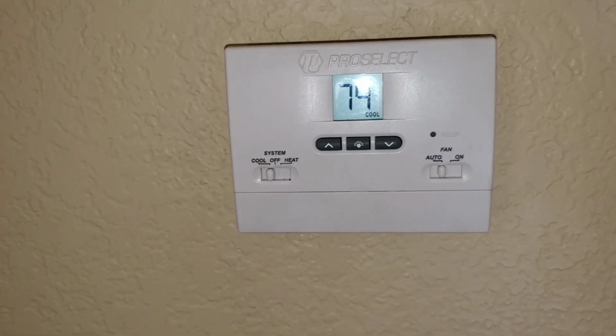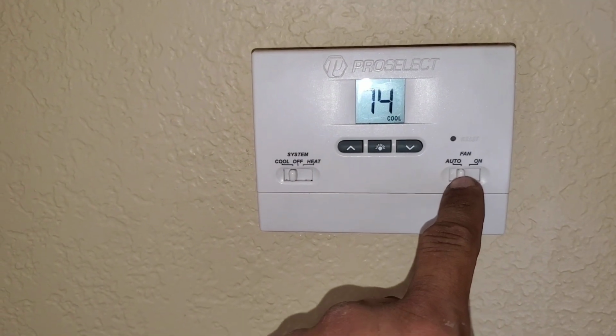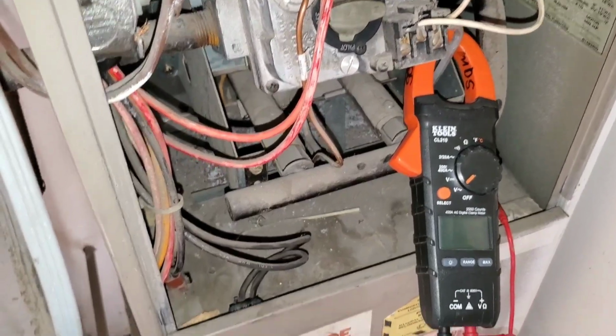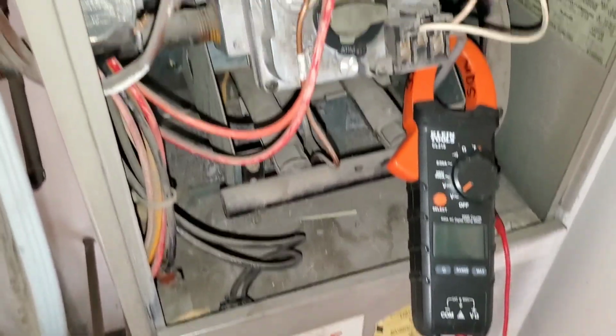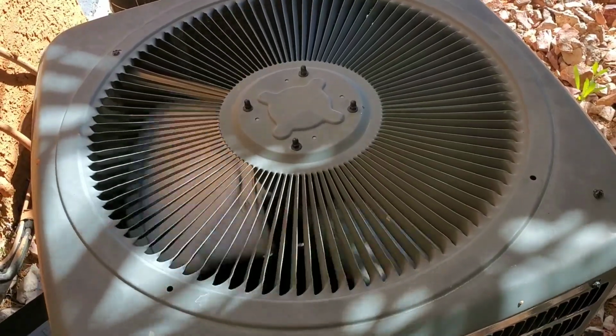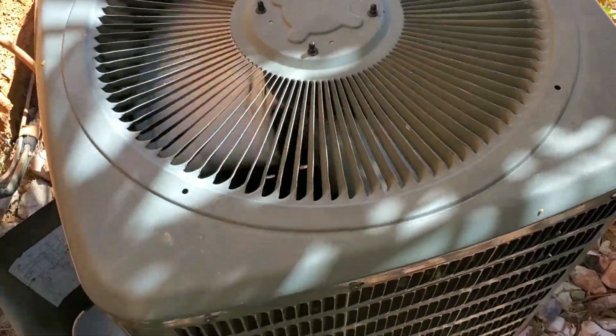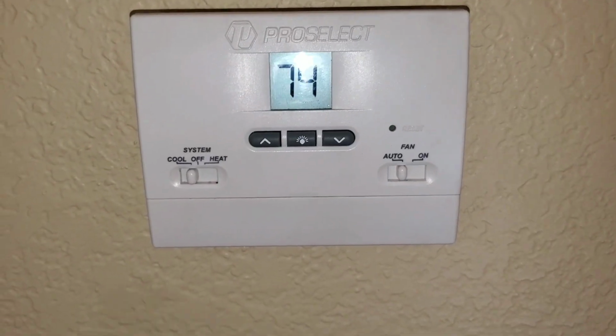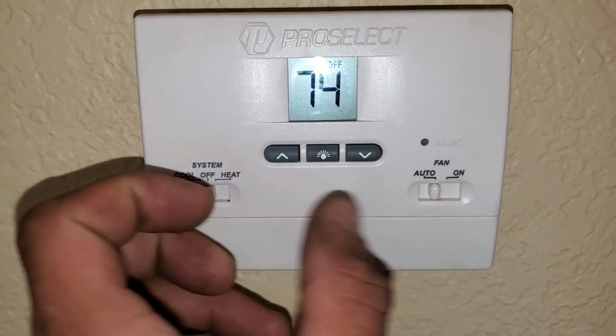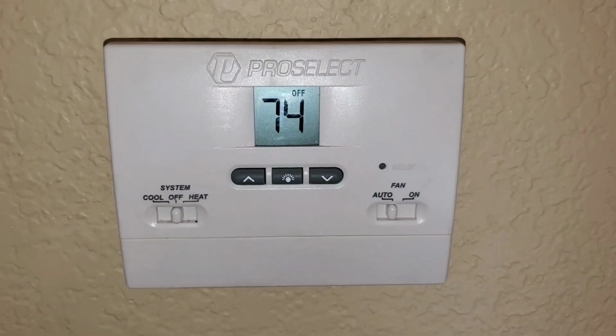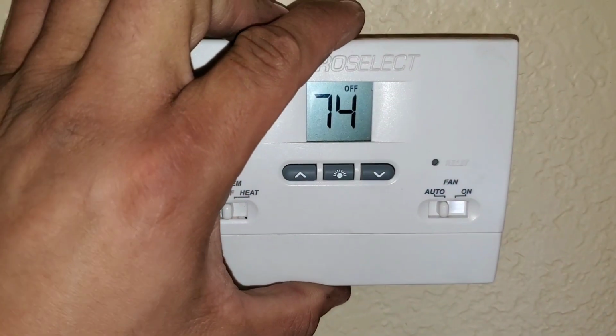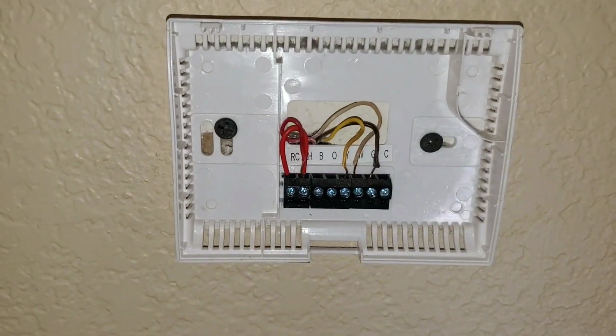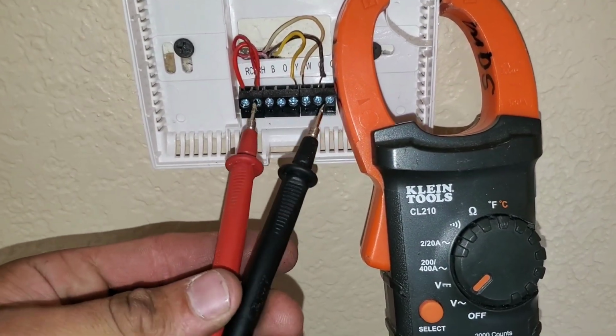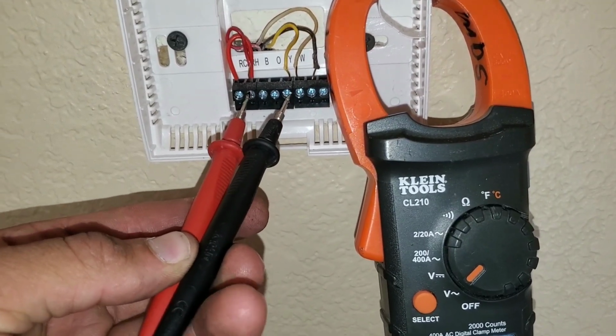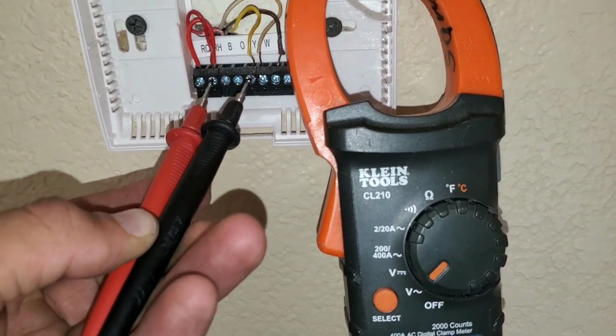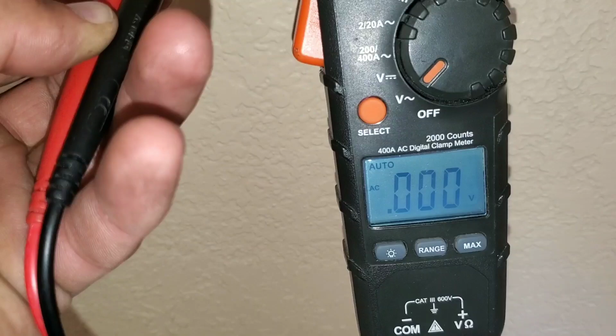Start at the beginning, thermostat is set, my blower motor at the return is running, my condenser is on. We're going to set our thermostat to off and auto. We're going to remove the face of our thermostat. If you run into an issue where you're not getting voltage at your thermostat, you're going to have to find out why you're losing voltage.